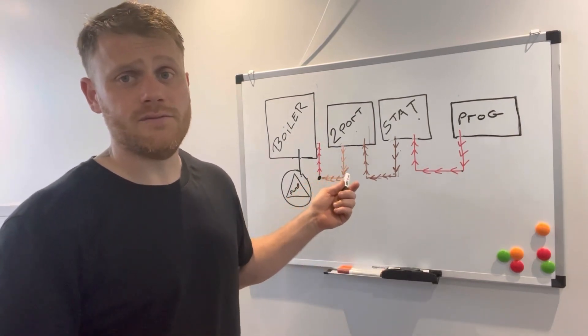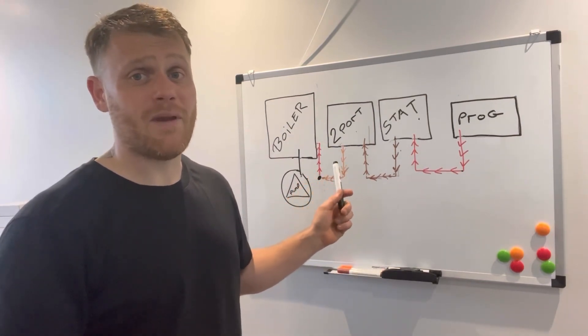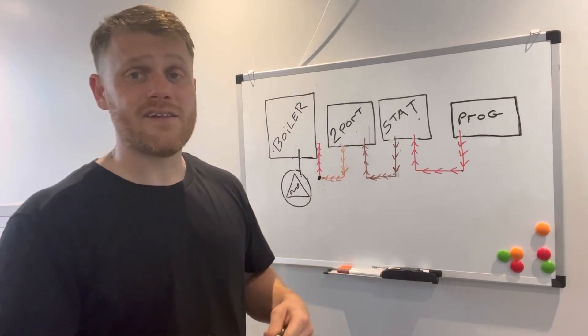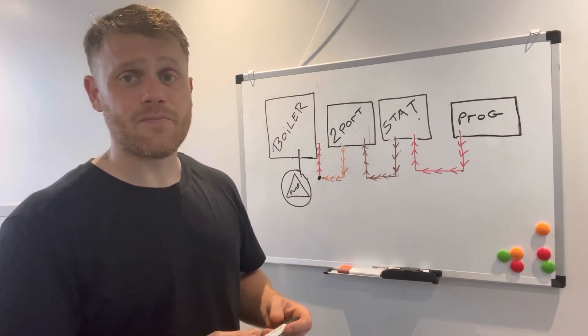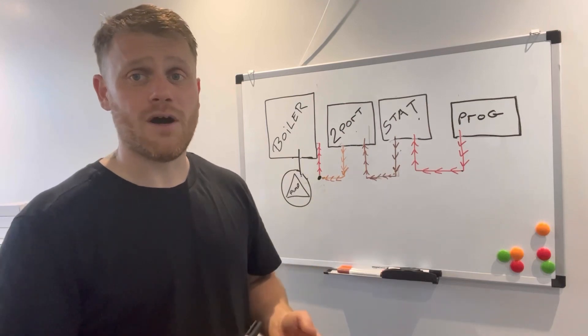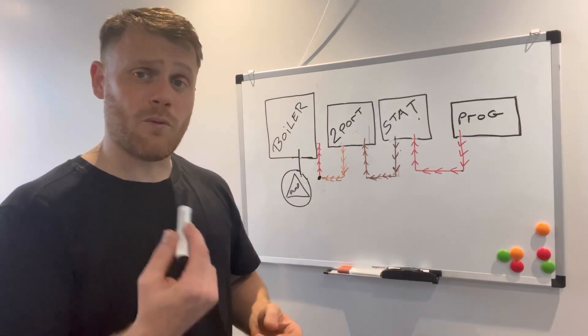Now if you do diagnose the two-port, it is worth mentioning most of the time you don't have to replace the full valve, and most of the time you don't have to replace the head. You can just do the synchron motor inside. You can just buy a replacement synchron motor.